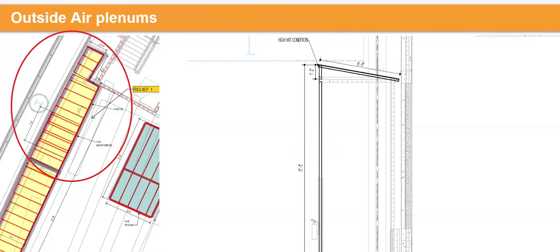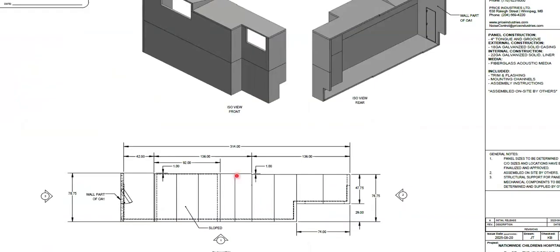On very large outside air plenums like this one, where you have a 17-foot tall plenum and it's 30 feet wide, this is going to need additional stiffening. You're going to have a ton of connections, structural steel, exposed metal all through this. If you do have very cold air at minus 15 degrees coming in within your space, you are going to have a lot of condensation on all the connections that you do have, which is where the thermally broken panel becomes the superior product. This is what it would typically look like with all the connections, all the panel layouts, all the thermal bridges through it as well.